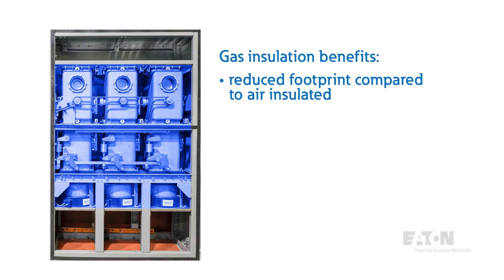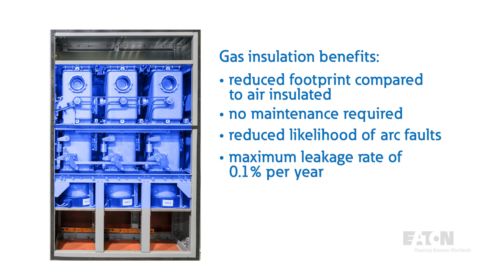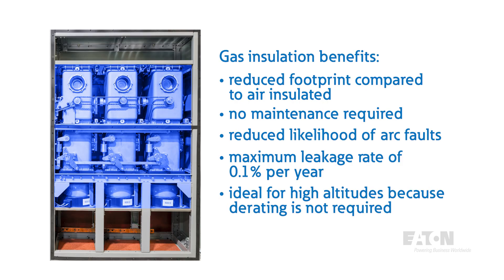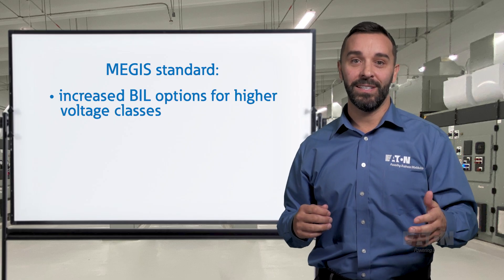With the main power components installed in hermetically sealed tanks, there is no maintenance required and a reduced likelihood of arc faults, preventing downtime of the equipment. The tank is designed as a sealed pressure system with a maximum leakage rate of 0.1% per year by the standard. This design is ideal for high altitude installations as derating is not required as it would be for air insulated applications. The MEGIS standard also enables increased BIL options for higher voltage classes.